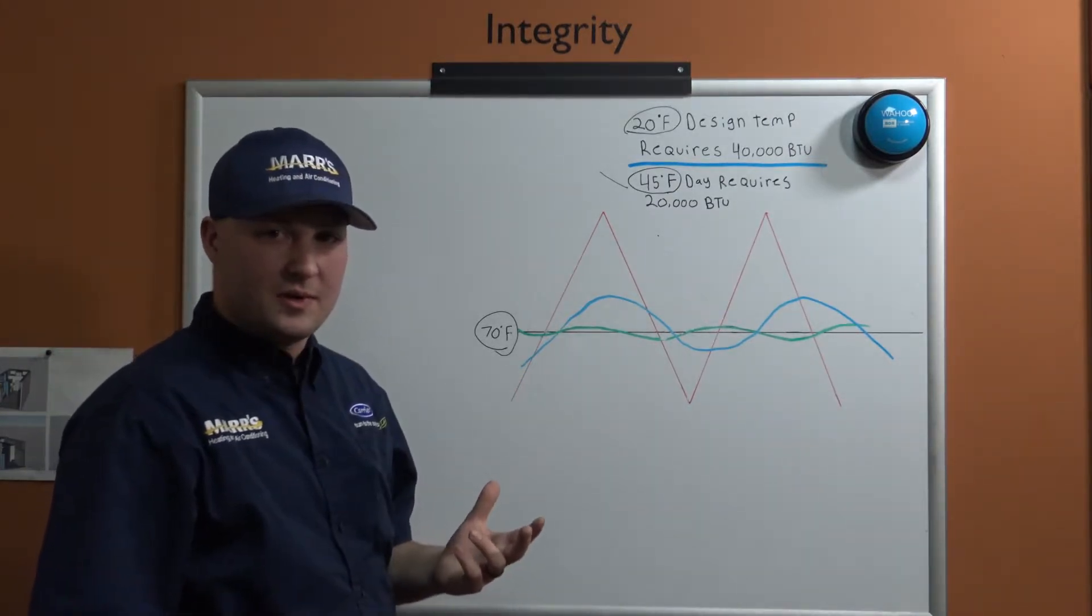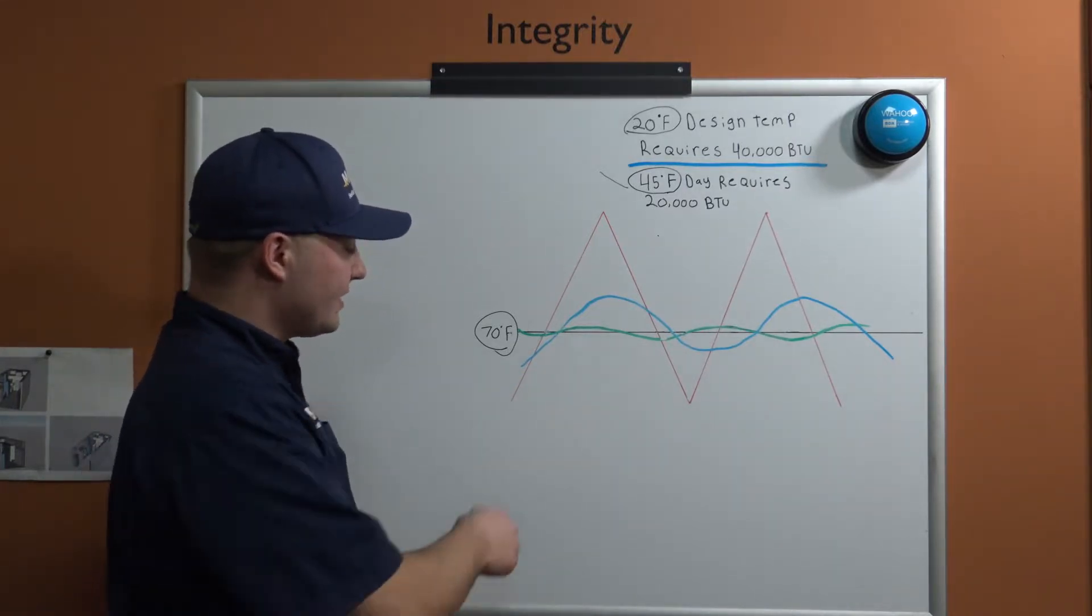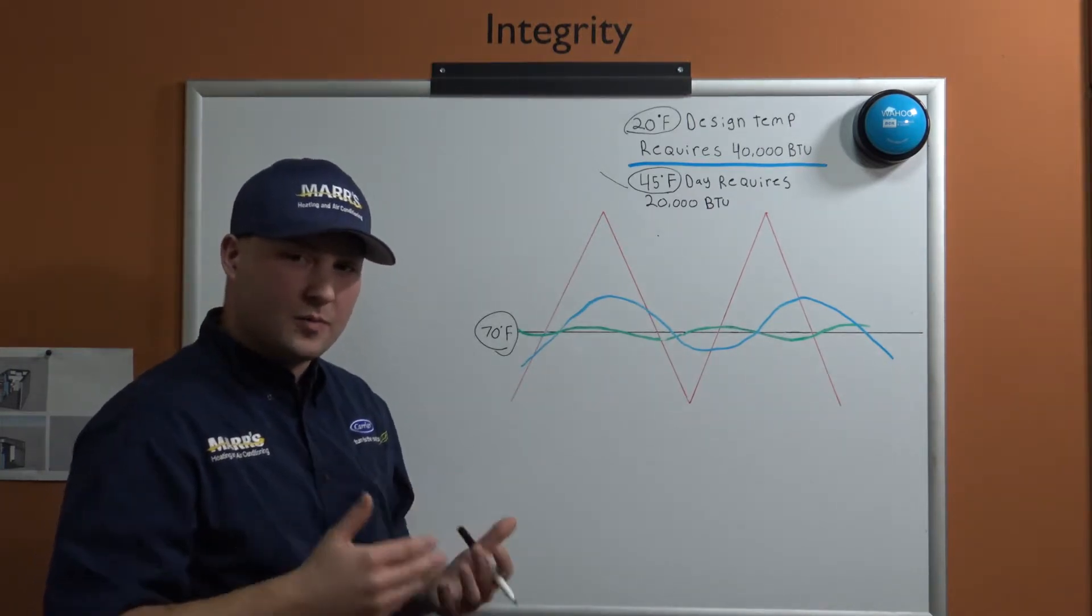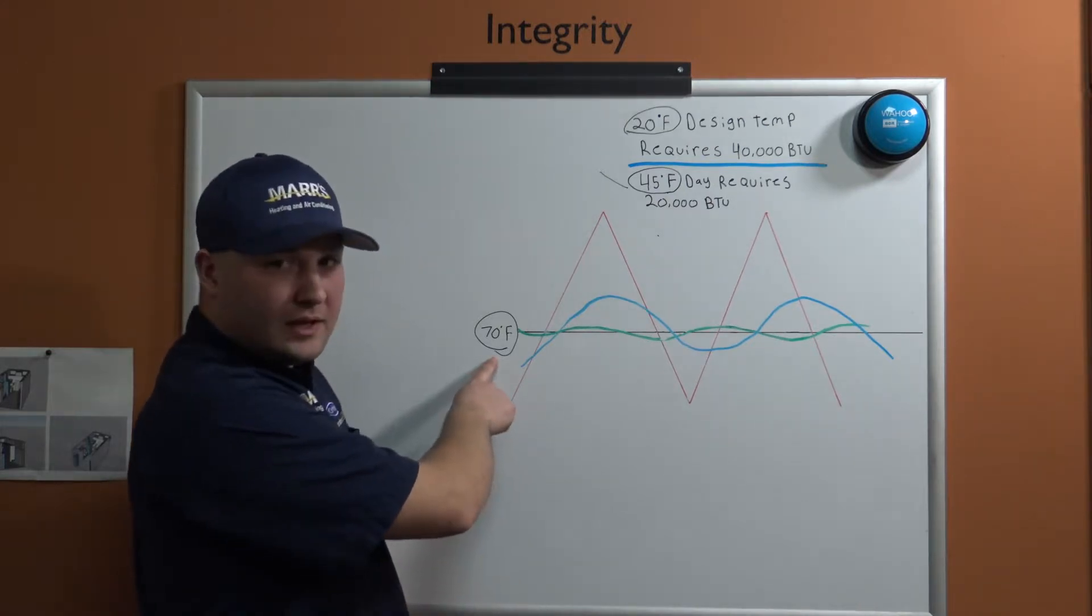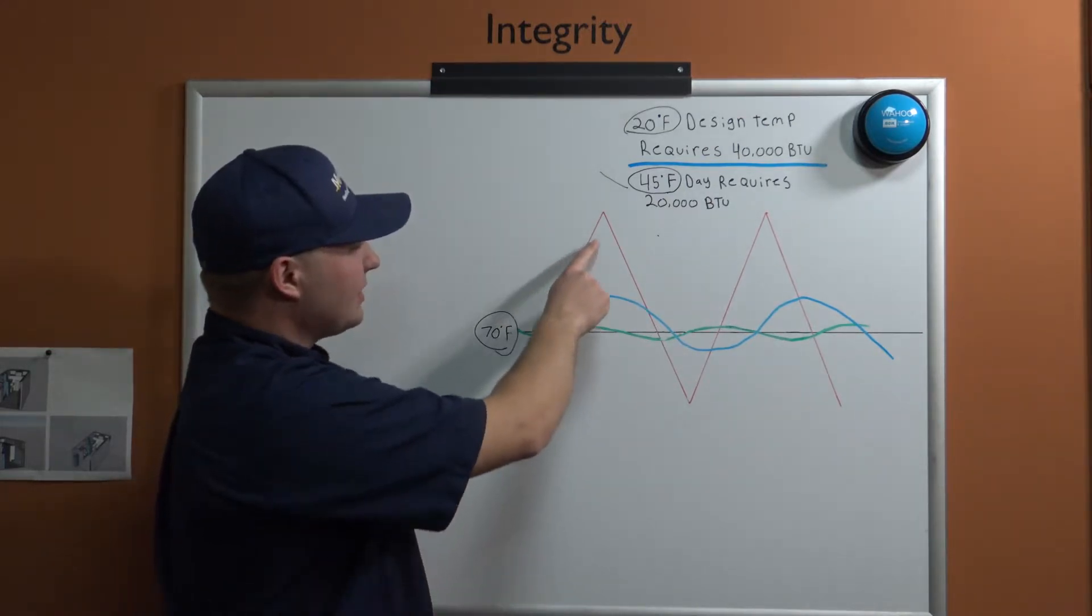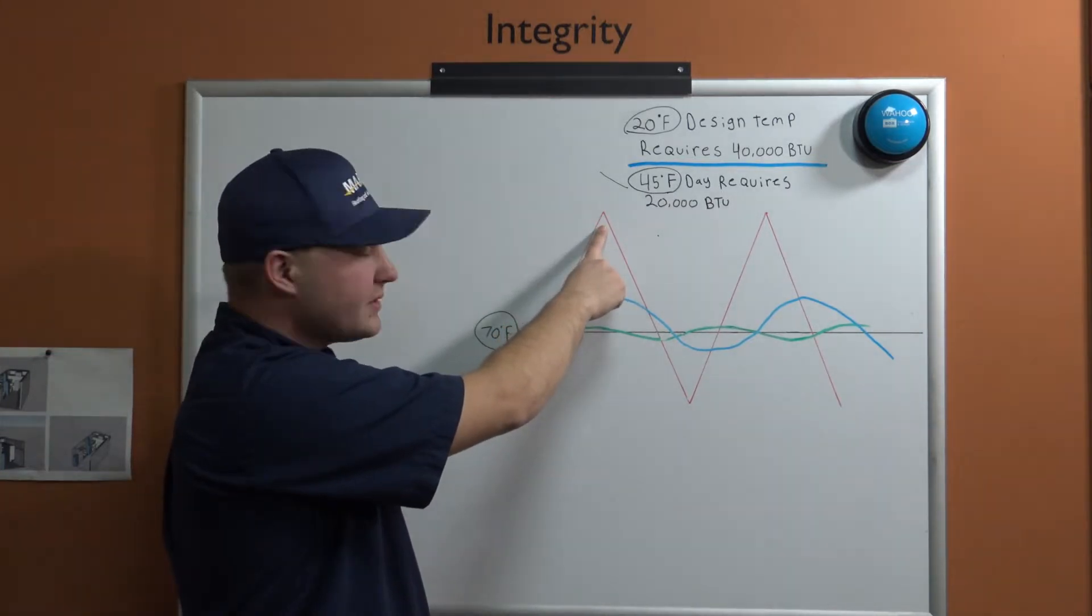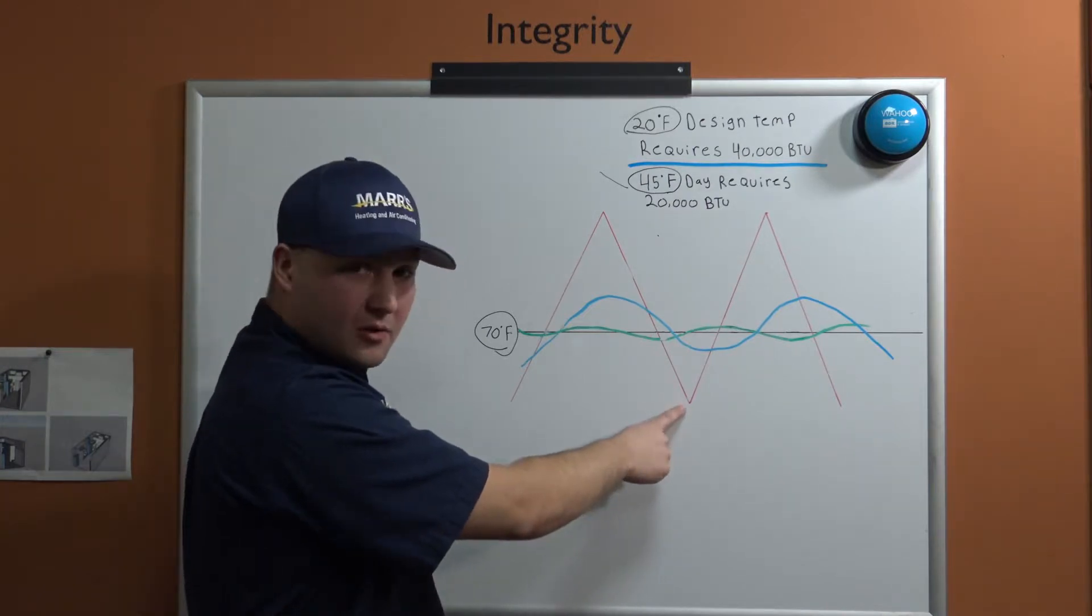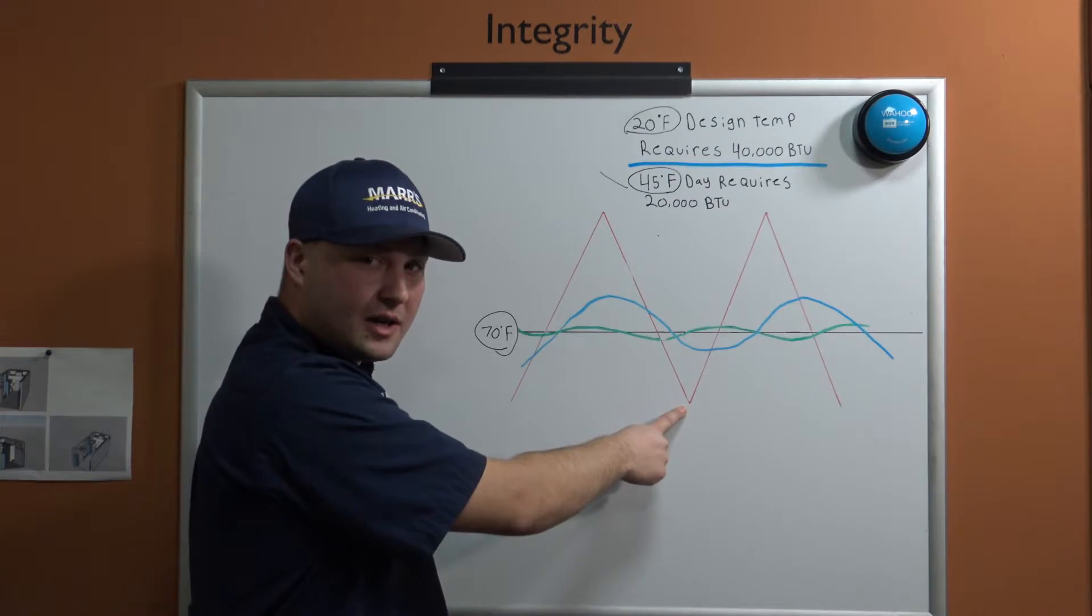With that, I'll start with single-stage equipment. Single-stage is outlined here in red. A single-stage piece of equipment is pretty simple to understand—it's either 100% on or 100% off. When we have a call for heat, we're going to actually overshoot that 70 degree mark by about three degrees, and then we're going to wait until we drop below our set temperature by about three degrees before we kick back on again.